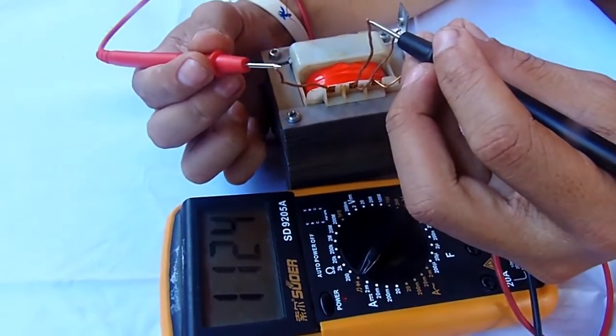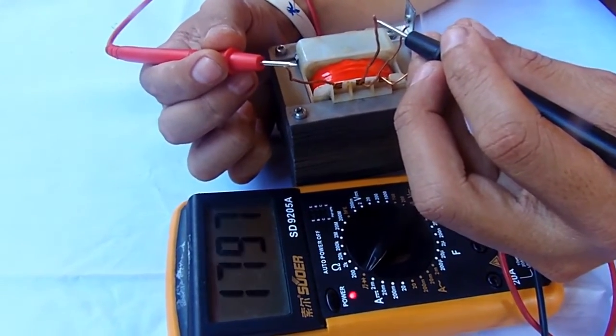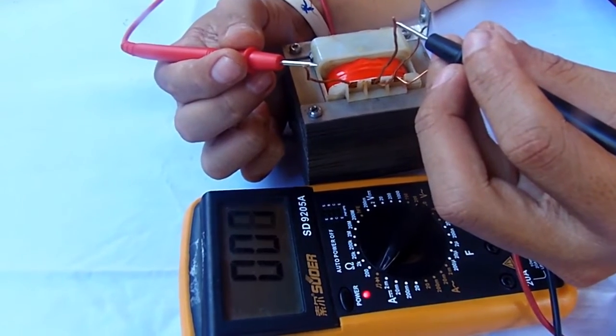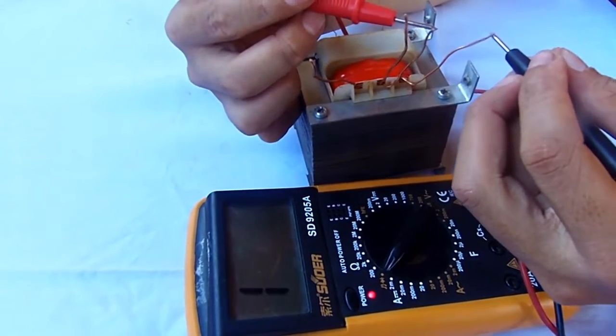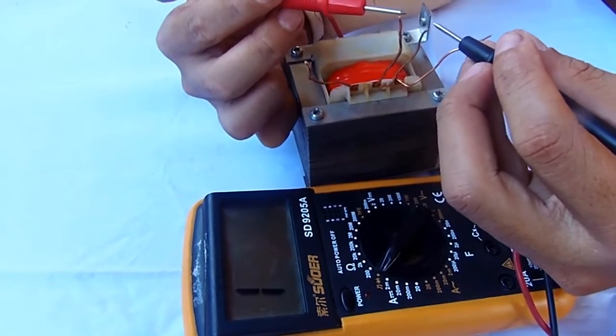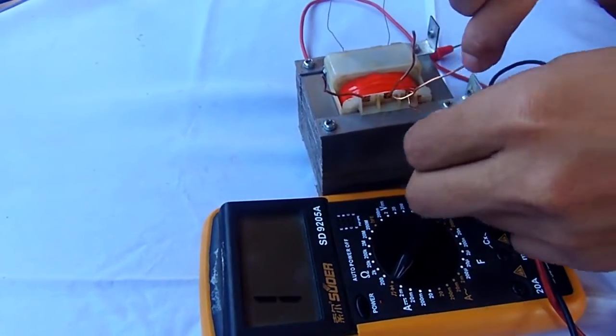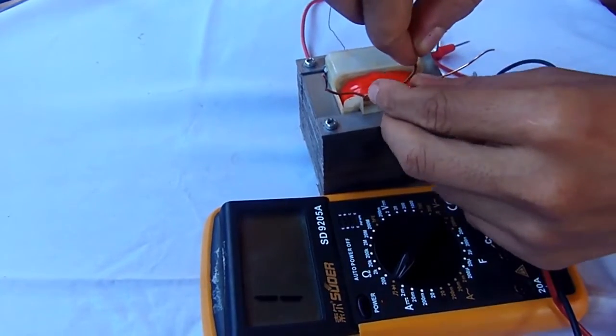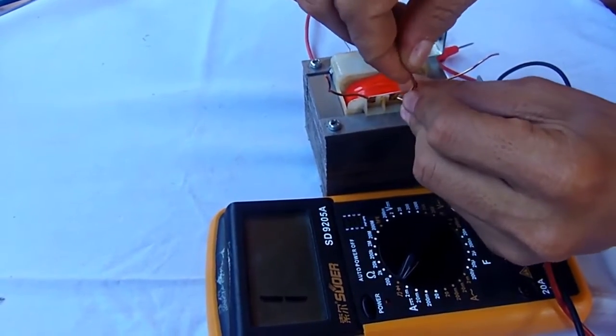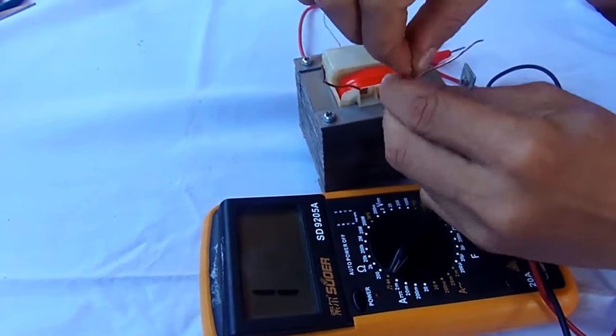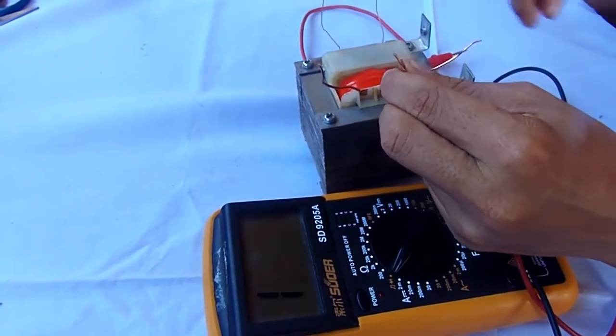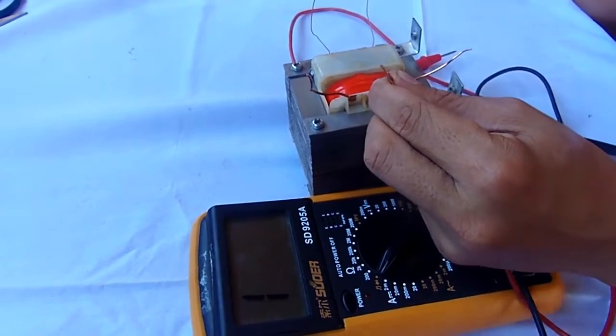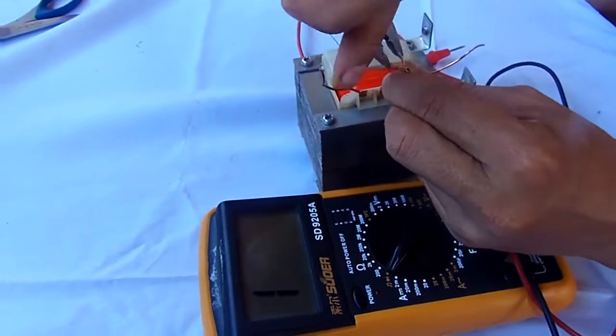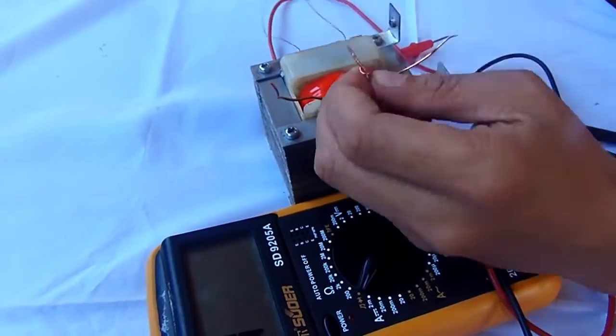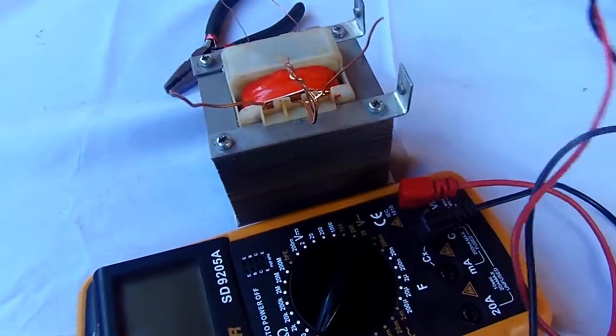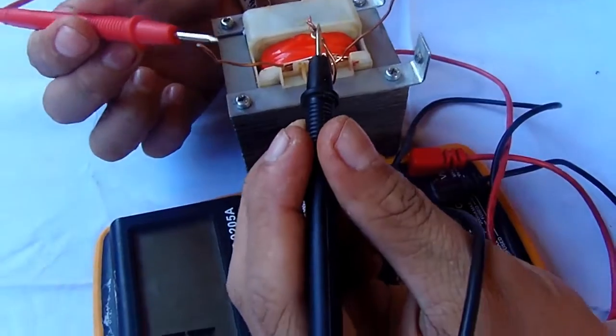Locating the center tap. To locate the center tap, check the continuity of each copper wire edge. It is necessary to join the leading edge of the winding with the other tail of the winding. And then check again the continuity for assurance.